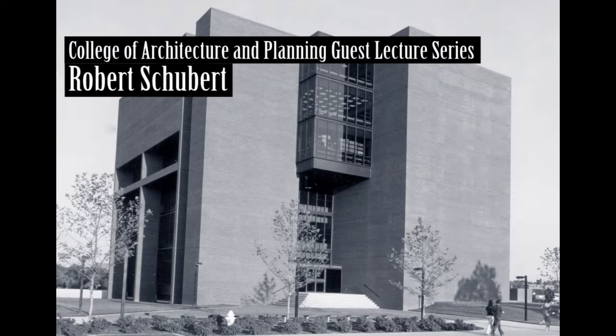This gives you a better idea of what's happening — this is the summertime operation. What separates summertime from wintertime operation are the location of the dampers. In wintertime operation, the dampers at the top would be closed, the interior damper would be open, and air could be circulated into the space. This wall could experience a backflow effect at nighttime temperatures, which would suck temperature through the collector and conduct heat away from the living space. That was taken care of by utilization of a thermal sink — cold air would come in and settle at the bottom, no longer continuing through the collector.